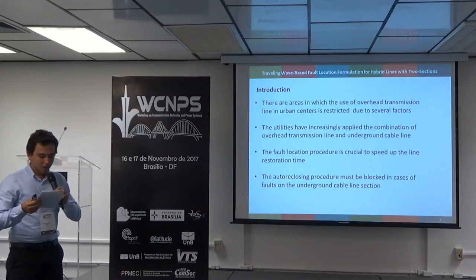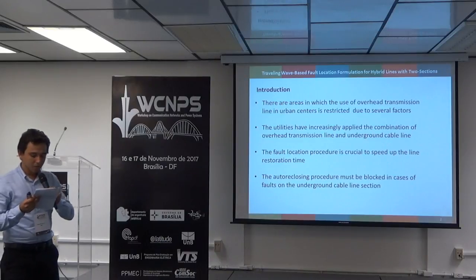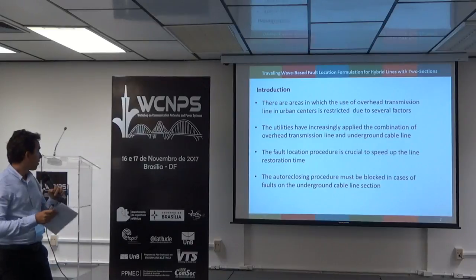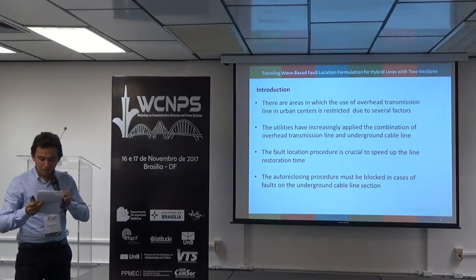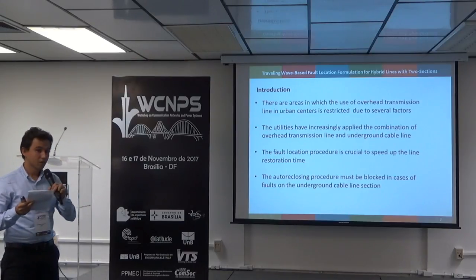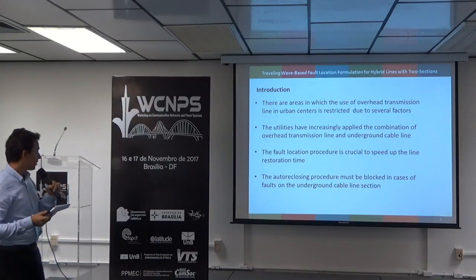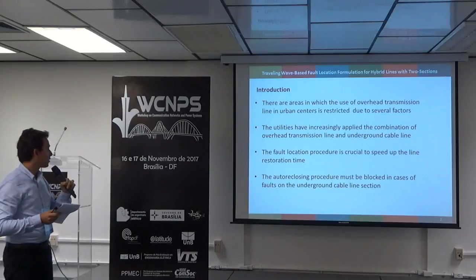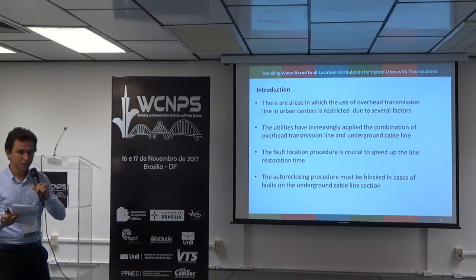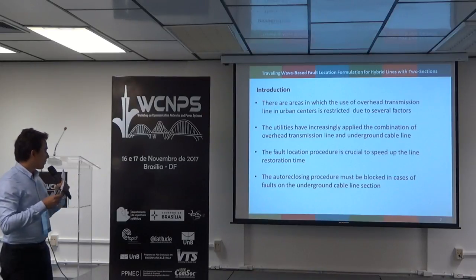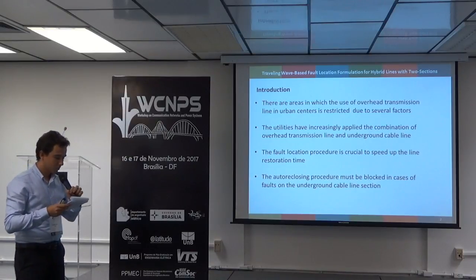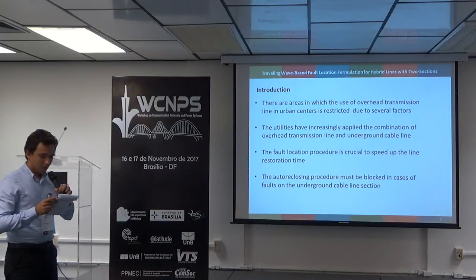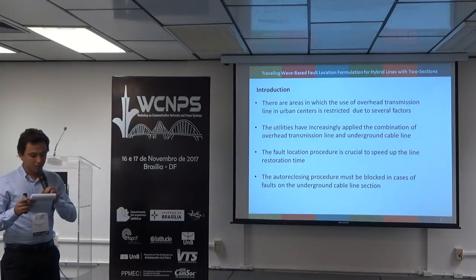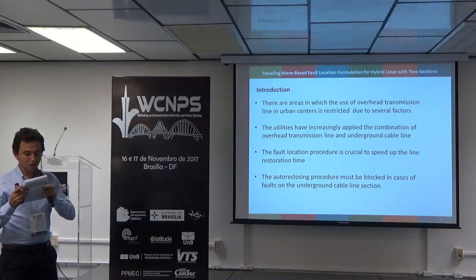A brief introduction and motivational points about this study on fault location in hybrid transmission lines. There are areas in which the use of overhead transmission lines is restricted due to several factors, such as visual impact and physical limitations. The utilities have increasingly applied the combination of overhead transmission line and underground cable line, resulting in hybrid transmission lines. The fault location procedure is crucial to speed up the line restoration time and provide support for the auto-reclosing procedure that must be blocked in faults on the underground cable line section.